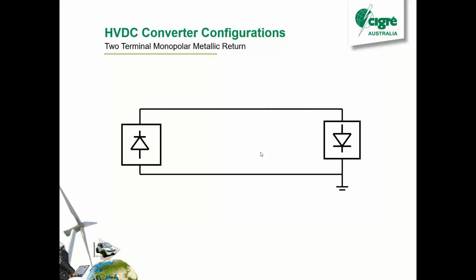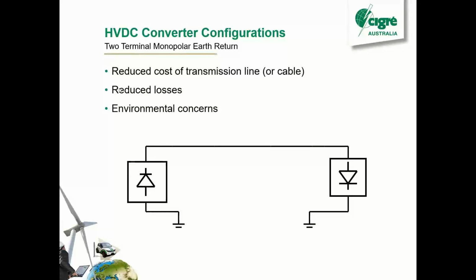But anyway, this diagram here is showing a two-terminal system. You have the sending end here, receiving end here, with a metallic return scheme. So you have a high voltage conductor on the top, and then you'll just have a low voltage wire going back to your sending end. You can also do earth return with HVDC. Earth return is quite cool because it means you can transfer power with just one wire between your sites. So that reduces the cost of your transmission line.